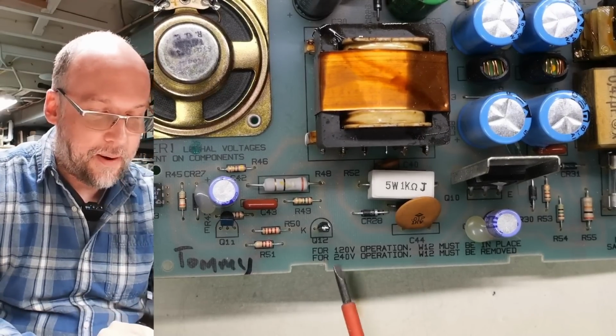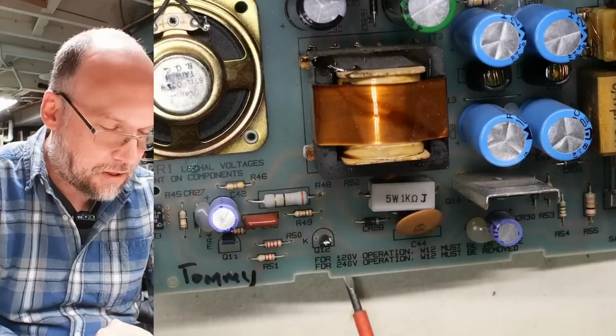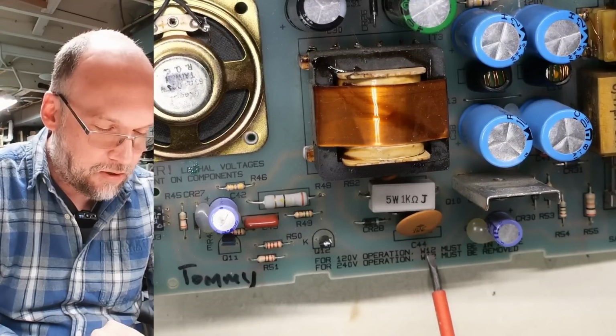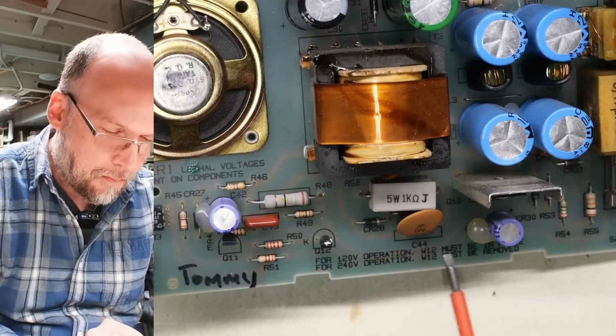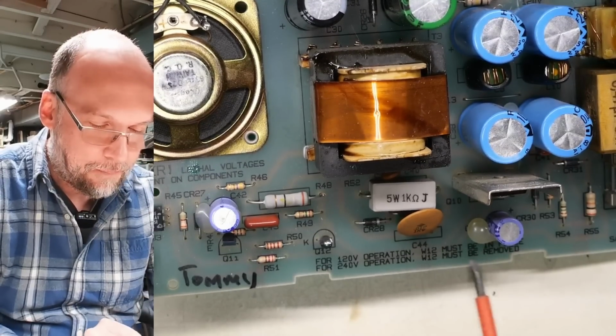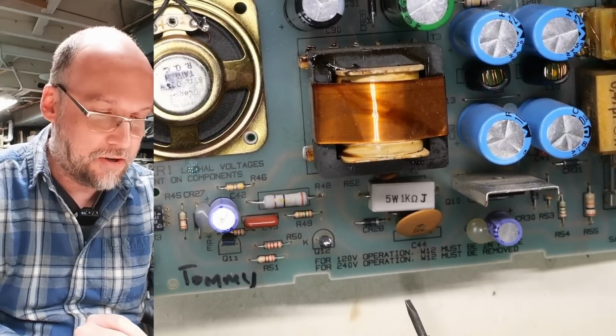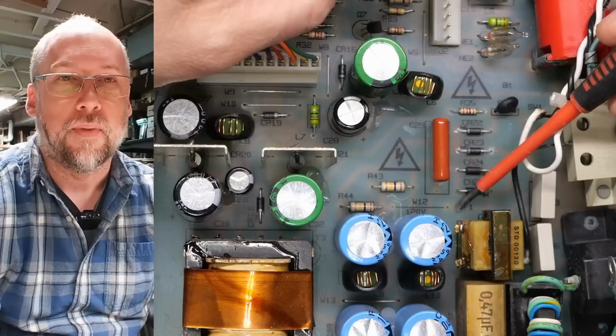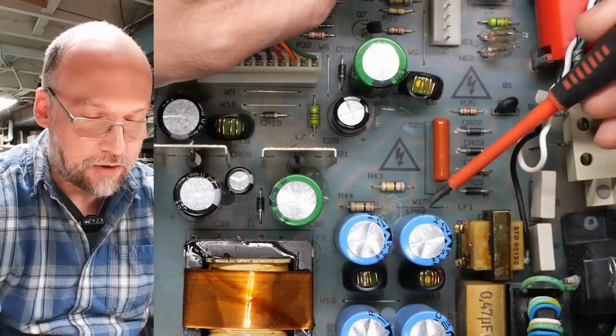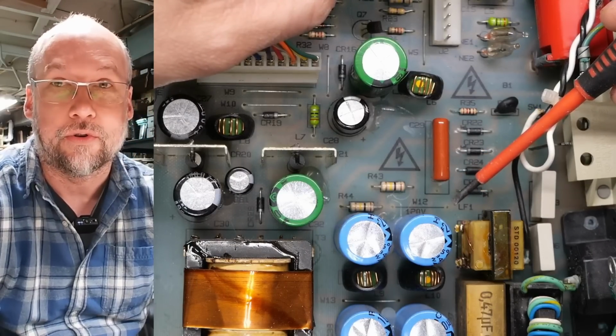Now, it does appear that this power supply is multi-voltage, and it says here for 120 volt operation, W12, which is a jumper link, must be in place, and if it's removed, the power supply runs in 240 volt mode. And right there is W12, and you can see it's removed, so this thing is configured for 240 volts.